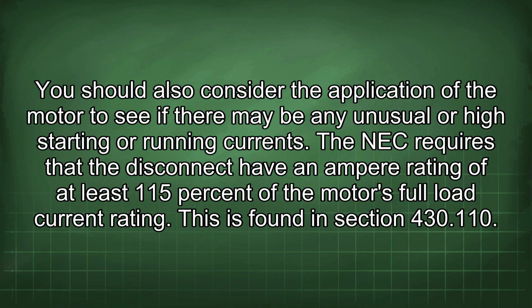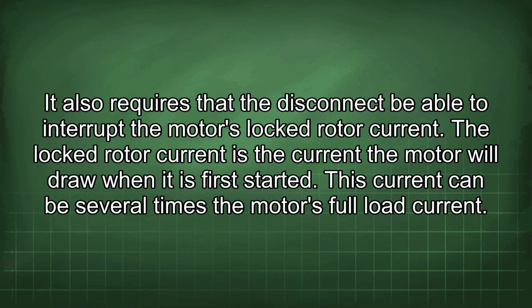You should also consider the application of the motor to see if there may be any unusual or high starting or running currents. The NEC requires that the disconnect have an ampere rating of at least 115% of the motor's full load current rating. This is found in section 430.110. It also requires that the disconnect be able to interrupt the motor's locked rotor current. The locked rotor current is the current the motor will draw when it is first started. This current can be several times the motor's full load current.